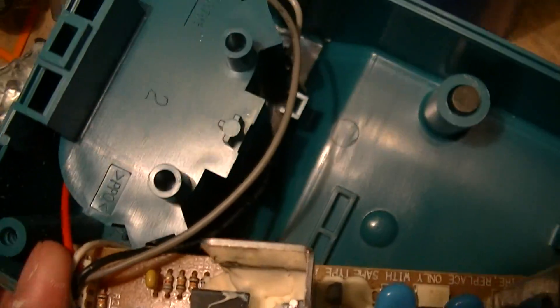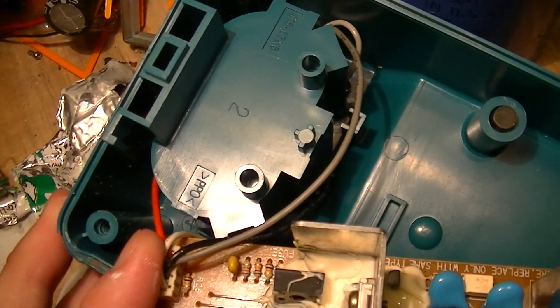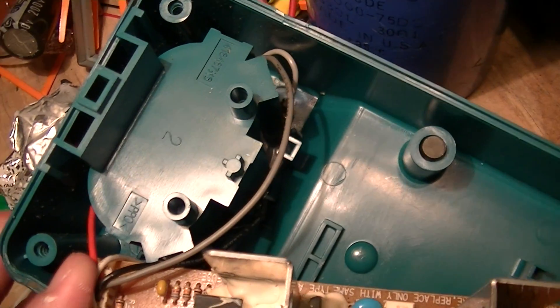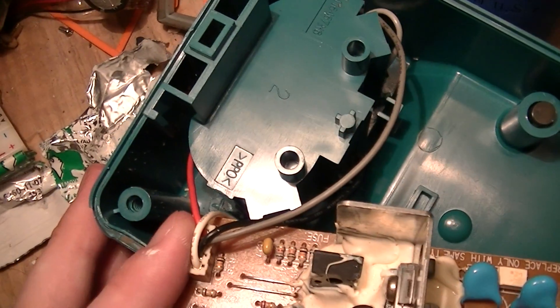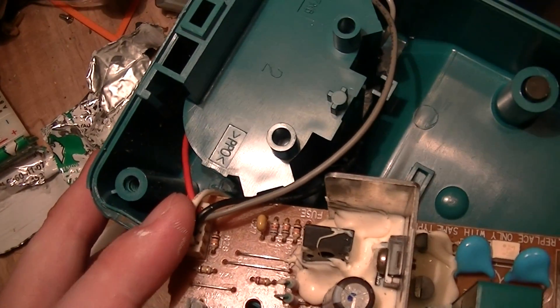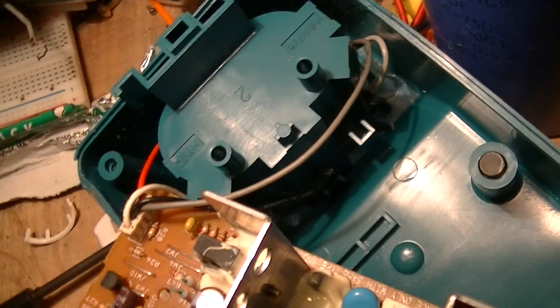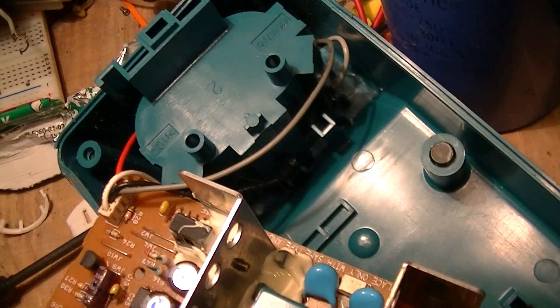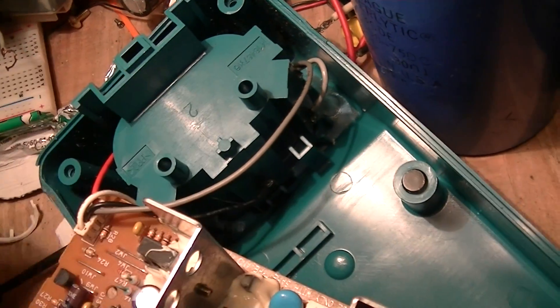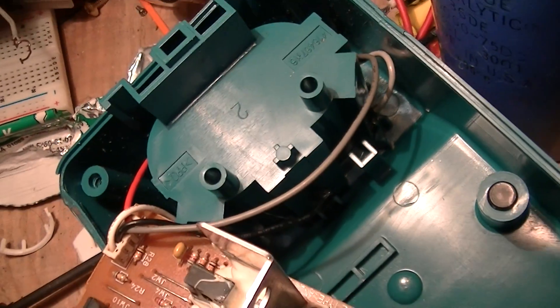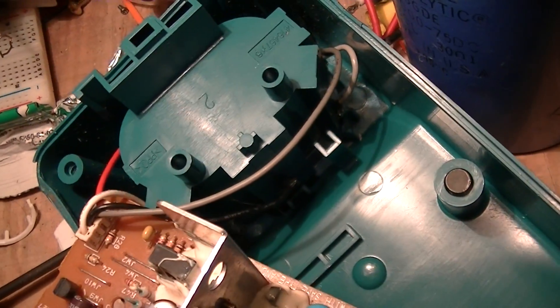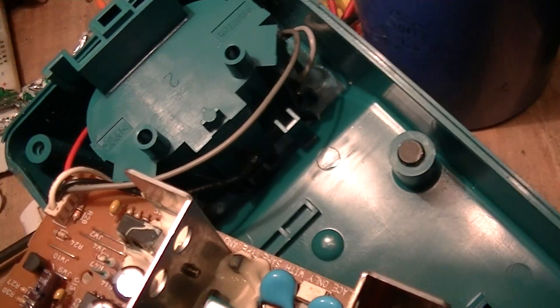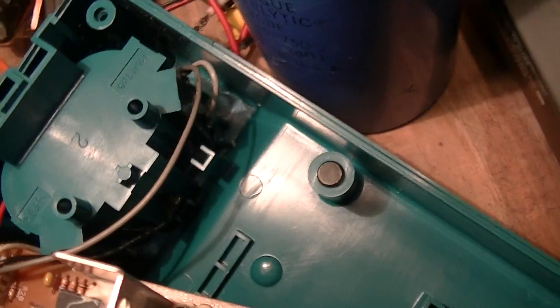And there's these, which are the outputs to the actual battery under charge. Two of which are DC hot and DC neutral for charging the battery. The other two go to things like thermistors in the battery and over temperature detection switches with a bi-metal switch in them as well.